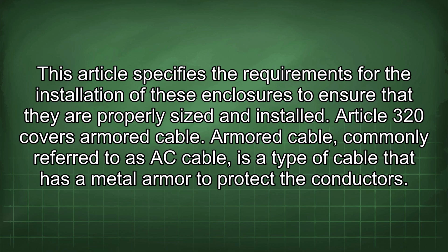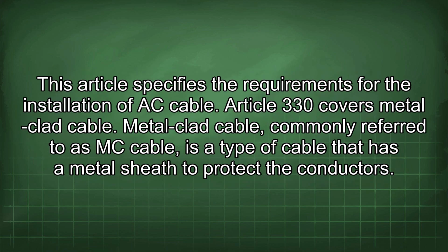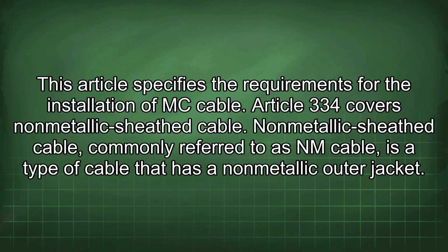Article 320 covers armored cable. Armored cable, commonly referred to as AC cable, is a type of cable that has a metal armor to protect the conductors. This article specifies the requirements for the installation of AC cable. Article 330 covers metal-clad cable. Metal-clad cable, commonly referred to as MC cable, is a type of cable that has a metal sheath to protect the conductors. This article specifies the requirements for the installation of MC cable.